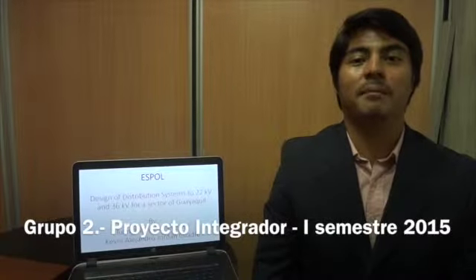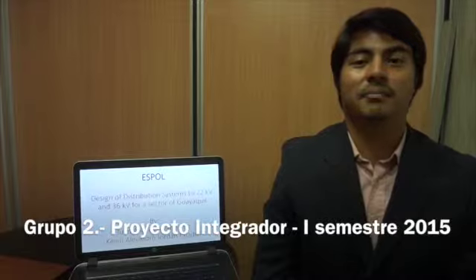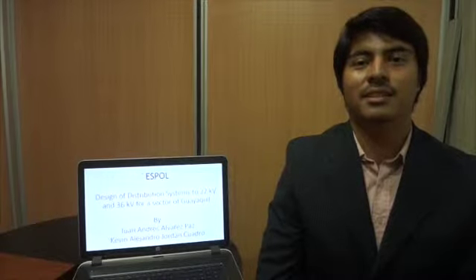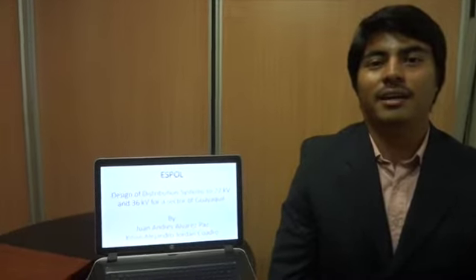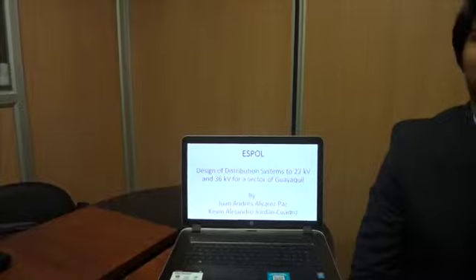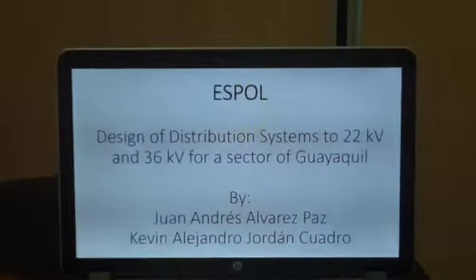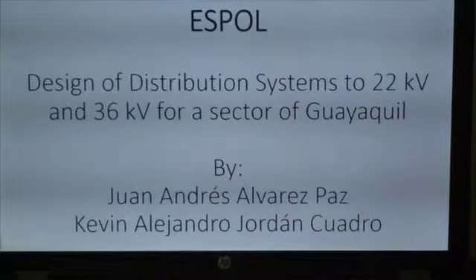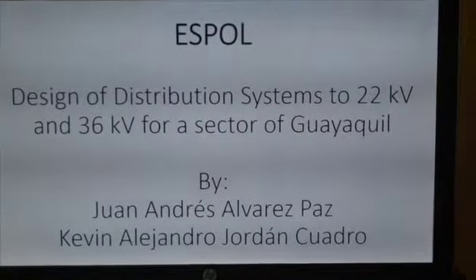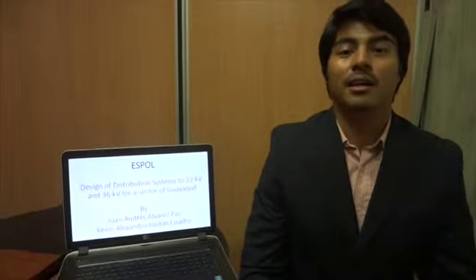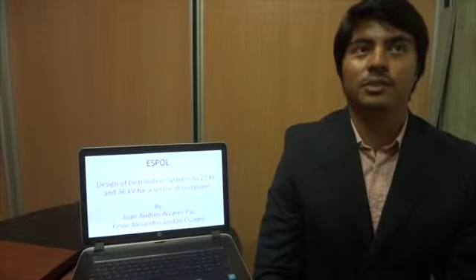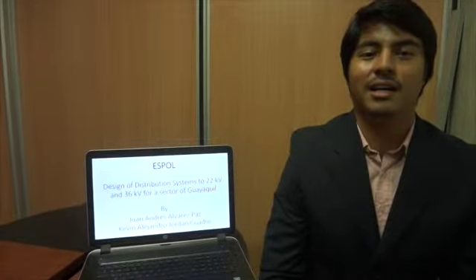Good afternoon. We will present the project developed in the integrative model, which is the design of a distribution system at 22 and 36 kilovolts for an area of Guayaquil. The electric utility system is usually divided into three segments: generation, transmission, and distribution. The distribution system, which is our main area of interest, is commonly broken down into three components: distribution substation, distribution primary, and secondary.